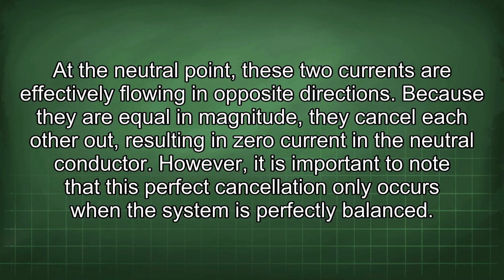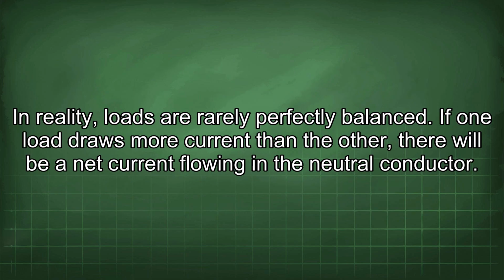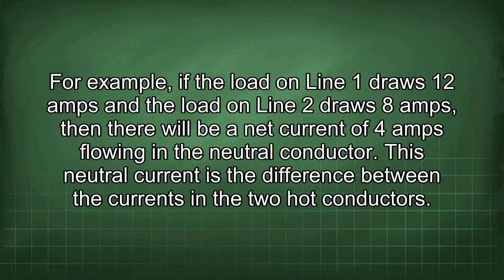However, it is important to note that this perfect cancellation only occurs when the system is perfectly balanced. In reality, loads are rarely perfectly balanced. If one load draws more current than the other, there will be a net current flowing in the neutral conductor. For example, if the load on line 1 draws 12 amps and the load on line 2 draws 8 amps, then there will be a net current of 4 amps flowing in the neutral conductor. This neutral current is the difference between the currents in the 2 hot conductors.